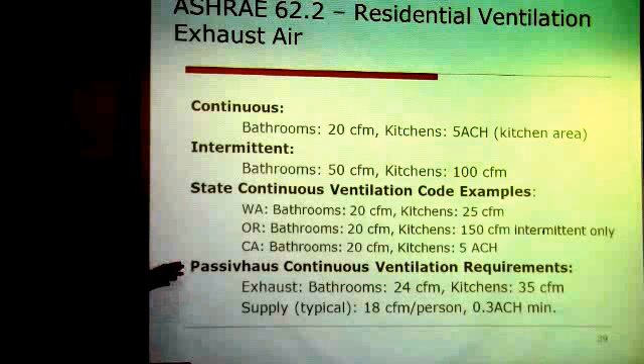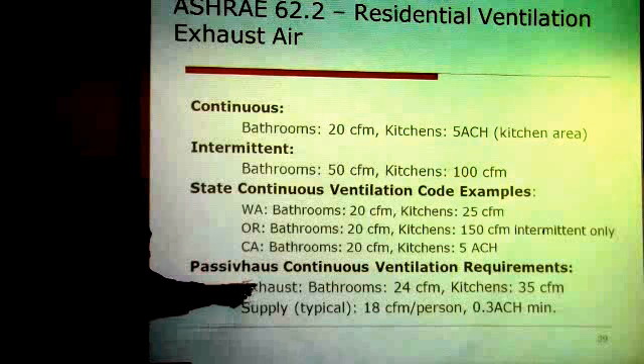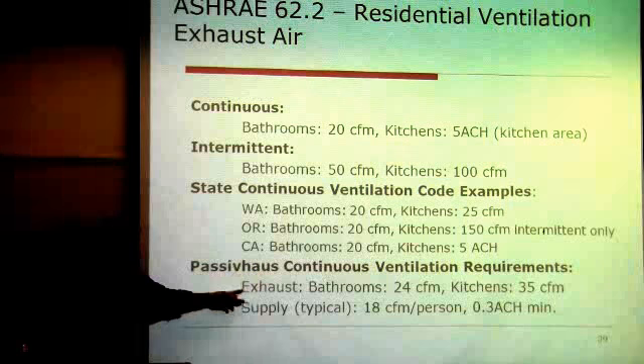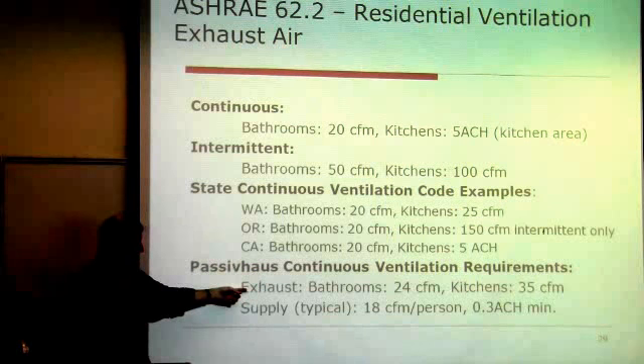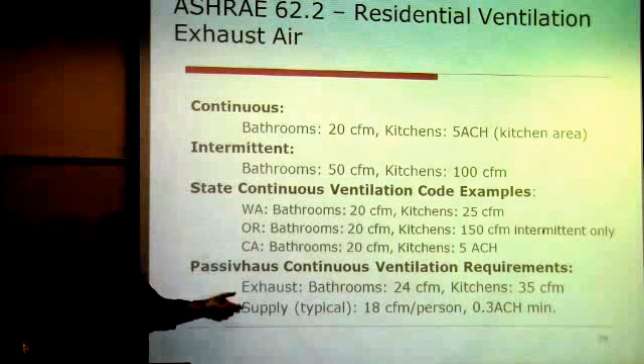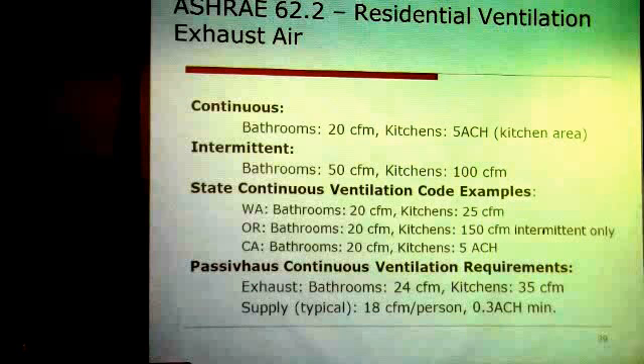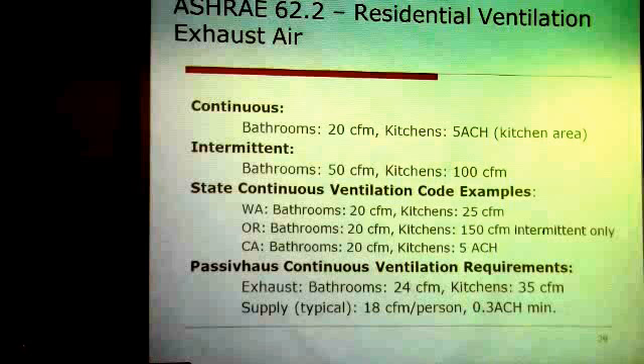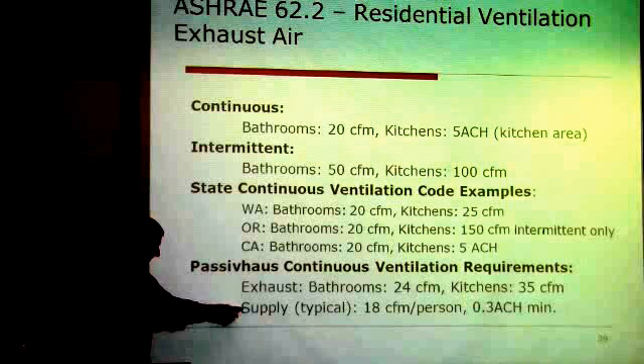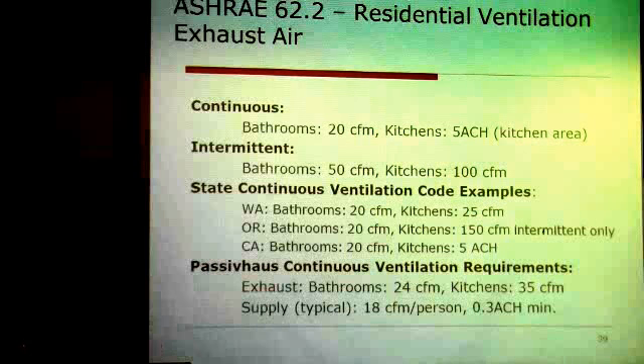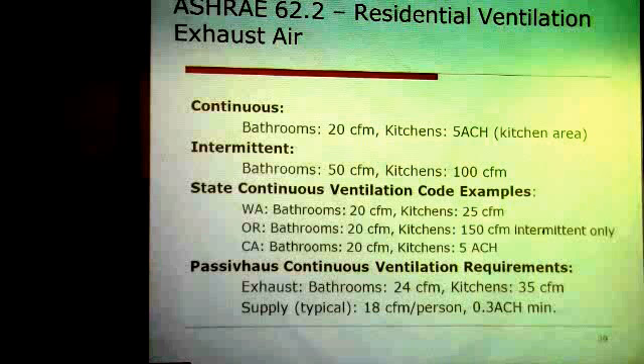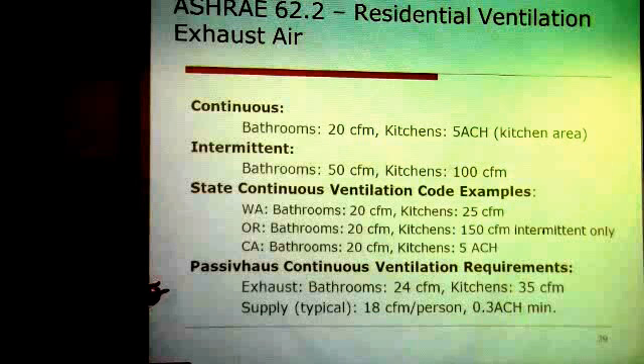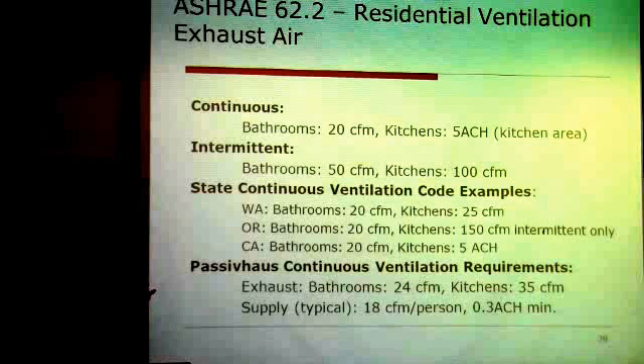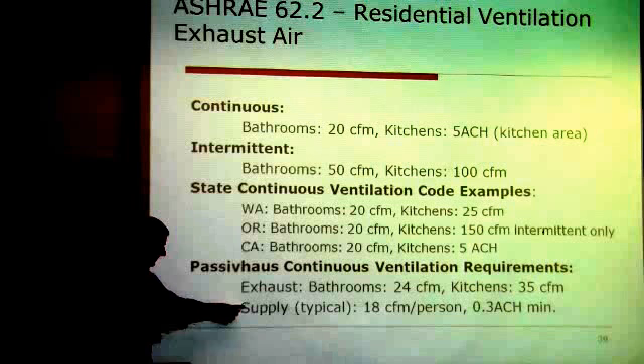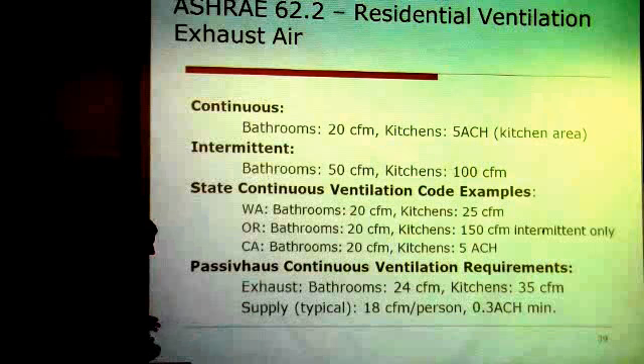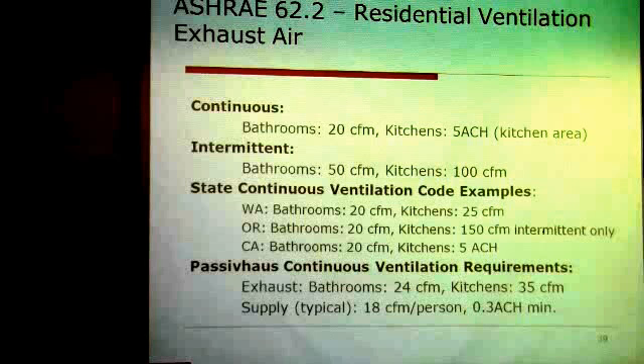And then in a passive house, the exhaust, bathroom 24, kitchens 35. So when you're designing in Washington, you just design for passive house and you meet this, and that's all. But with California or Oregon, you have to do some more to look at that. And then passive house supply is just 18 CFM per person. So back to that case of a 2,000 square foot house, 3 bedroom, 2 bath.